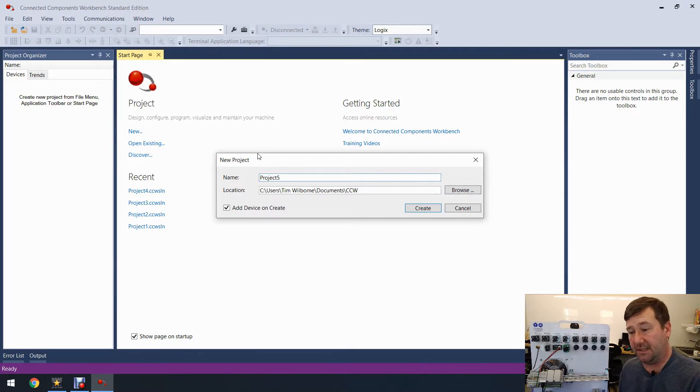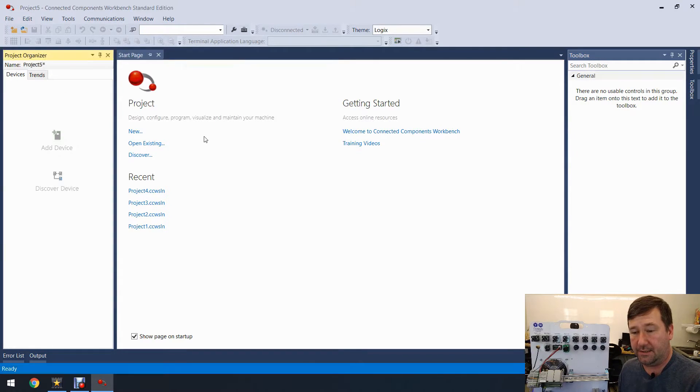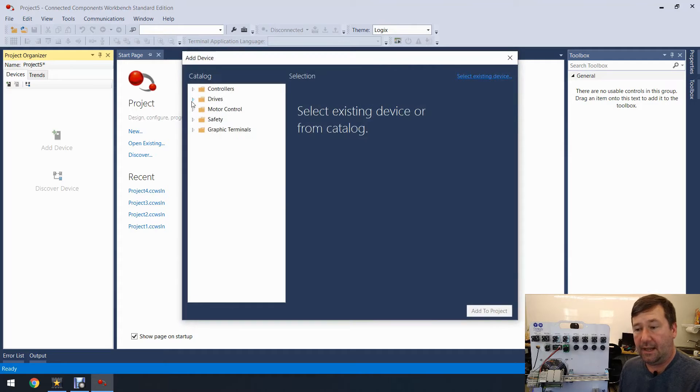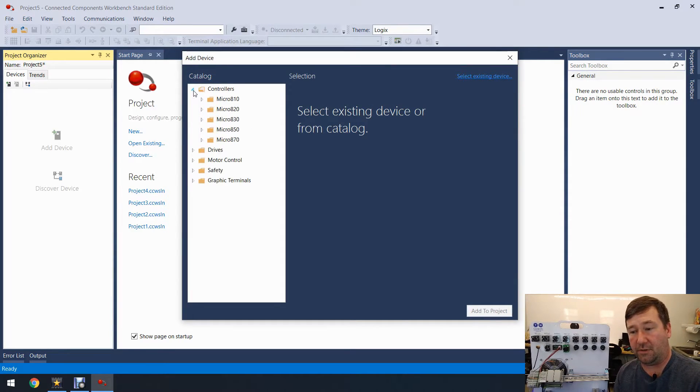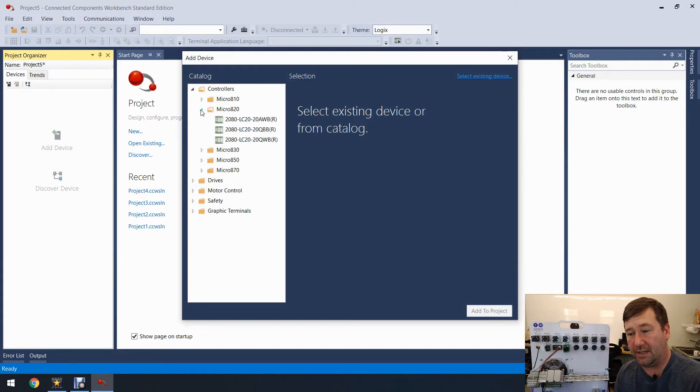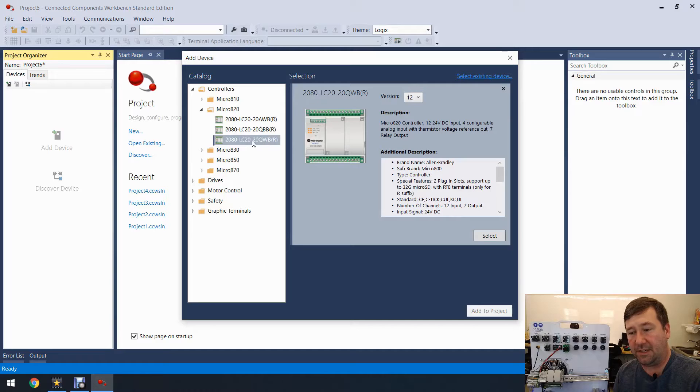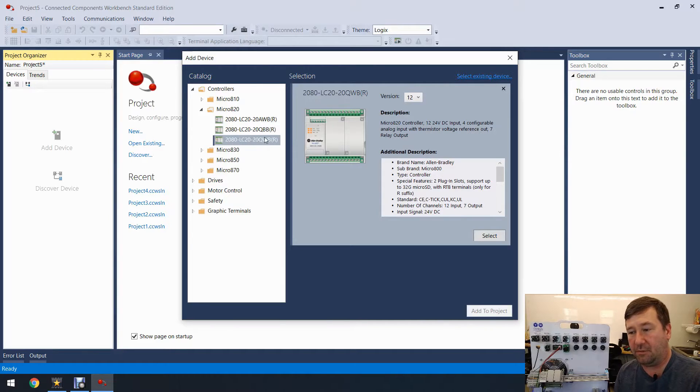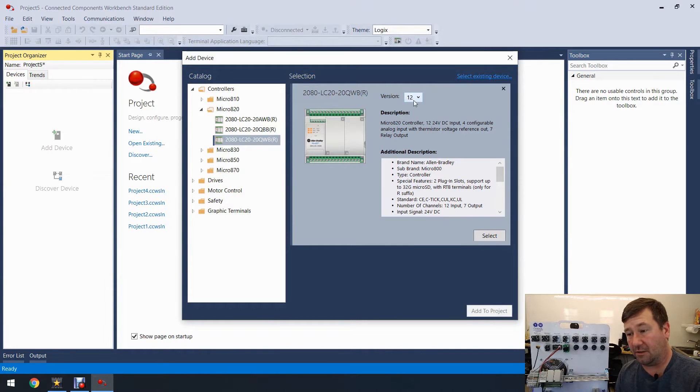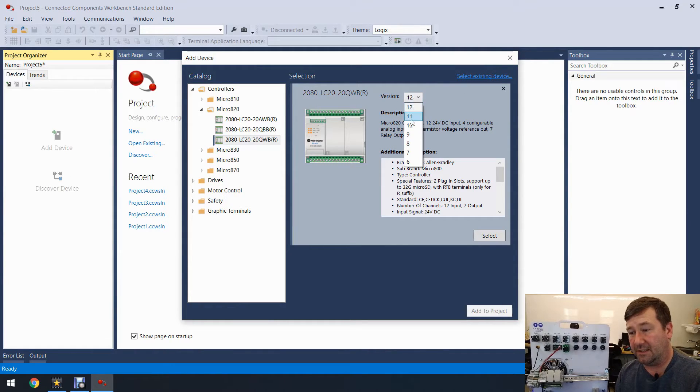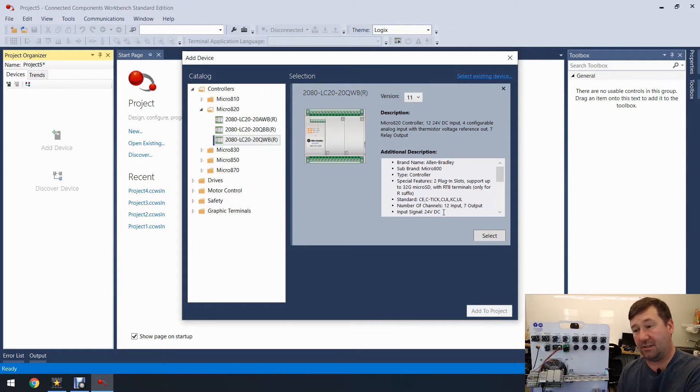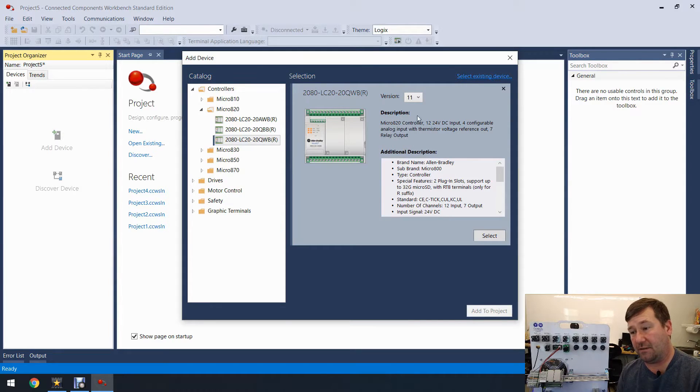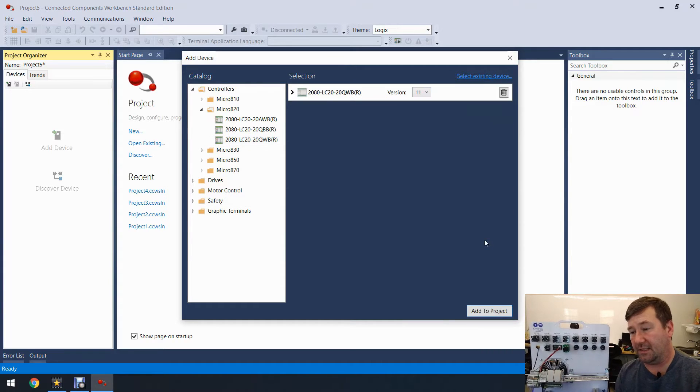Then it's going to ask us to select our device. So we're under controllers, we're going to find the Micro 820, and then we have a 2080-LC20-20-QWB. And from the IP explorer that we used to determine the IP address, we also learned that this is a version 11 processor. You've got to match the processor that's shown right here with what is in the PLC. So we'll select it and add it to the project.